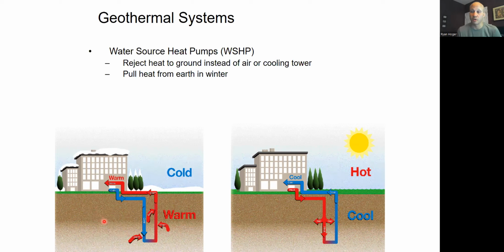So when it gets to the point of the winter, typically later in the winter, January, February, and the ground temp's not doing as good of a job because they don't have as much heat stored in the ground, the boiler will kick on to temper that water up a little bit more. If I did have a cooling dominated building, then I wouldn't need that boiler. Instead, I would have a supplemental cooling tower. I'm shoving more heat in the ground in the summer than I'm taking out in the winter. I need a cooling tower to trim off that difference.